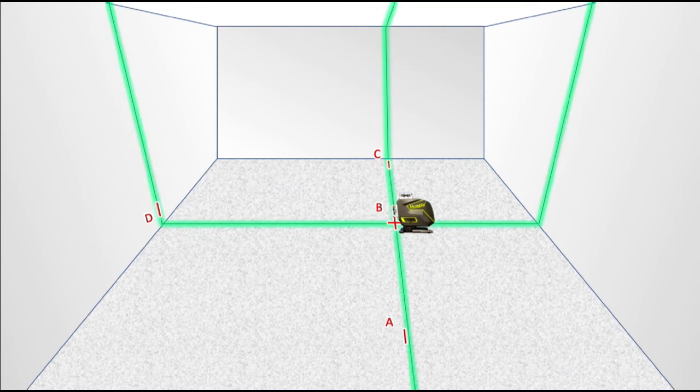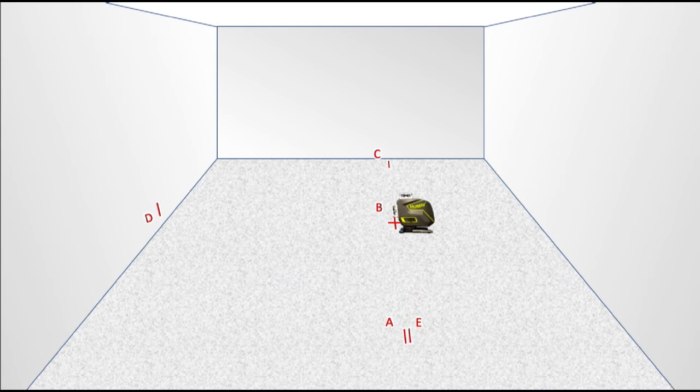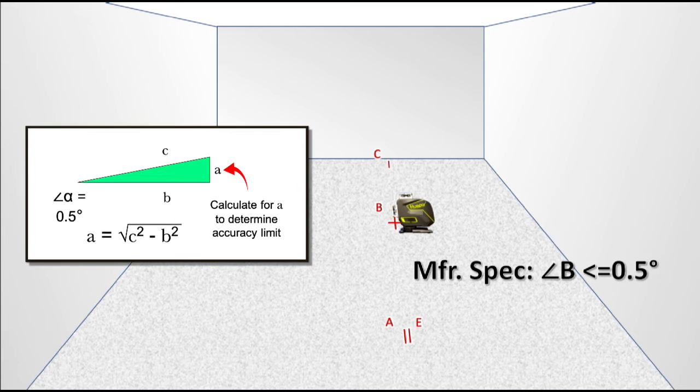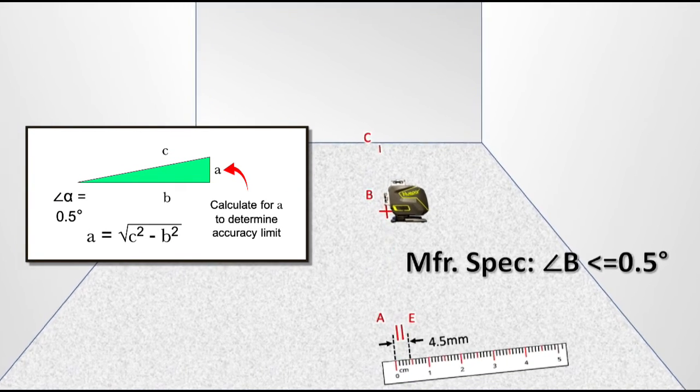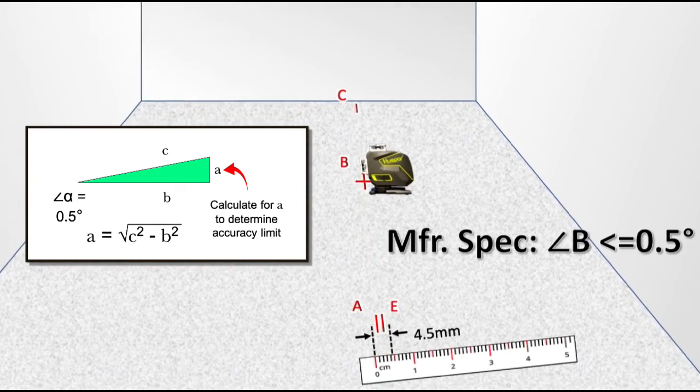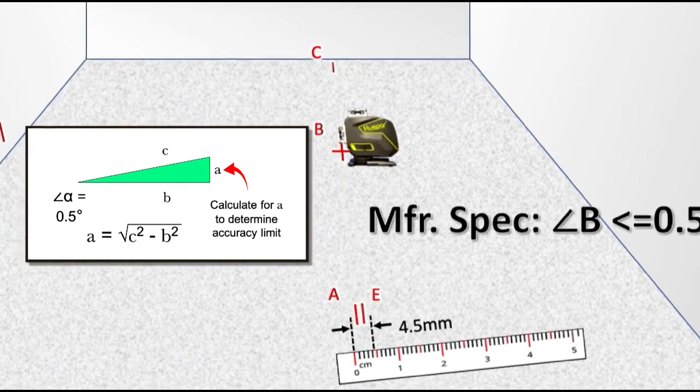Now, make a mark next to mark A and label this mark E. Note the distance between marks A and E. Also note that marks A and E join at B, creating an angle which cannot be more than one half degree. Since we are checking orthogonal accuracy at 5 meters, we can calculate for right triangle and determine that the maximum deviation is just less than 4.5 millimeters. In this simulation, we can see that the measure deviation is about 2 millimeters, so we are within manufacturer specification.